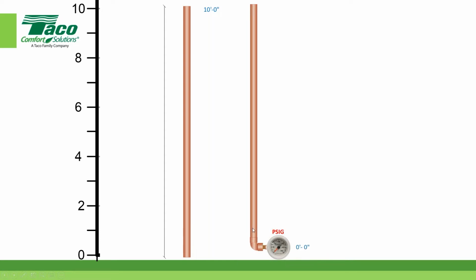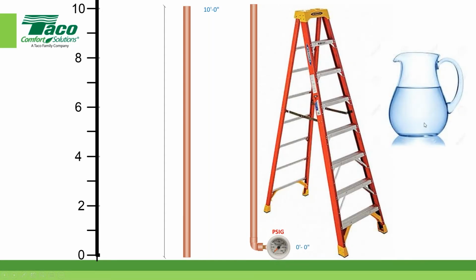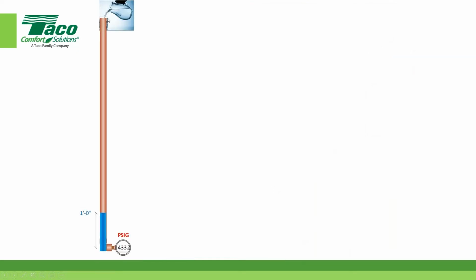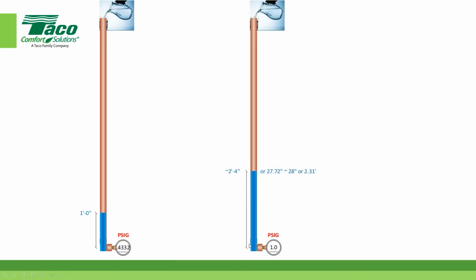So if I spend the money, I put a nice gauge on the bottom of this, I get myself a ladder and a bucket full of water or a pitcher full of water, and I start filling these things up to certain levels, okay? Now notice, if I go back to that number I gave you before, a 1 foot column in this pipe, let's say it's a 3/4 inch pipe, is going to be just under half a psi. If I get my ladder out and I put some more water in there and I get it up to that magic number of 2.31 feet, roughly 28 inches, I'm going to be at 1 psi. That's why we use these two numbers for conversion.